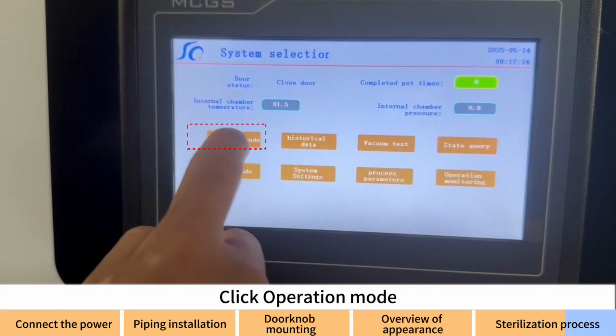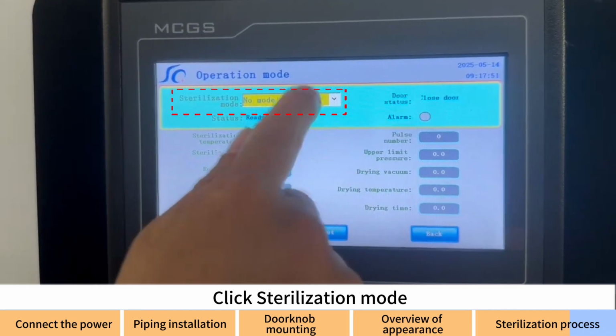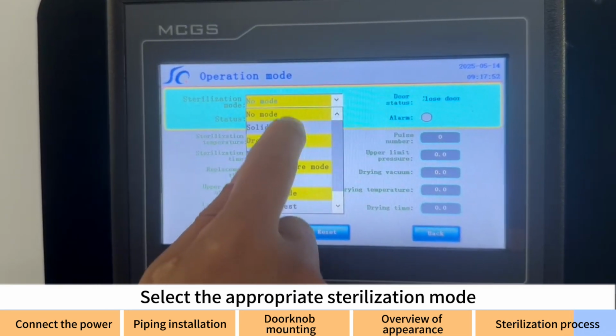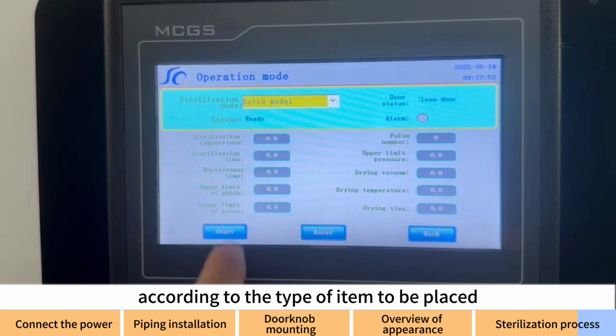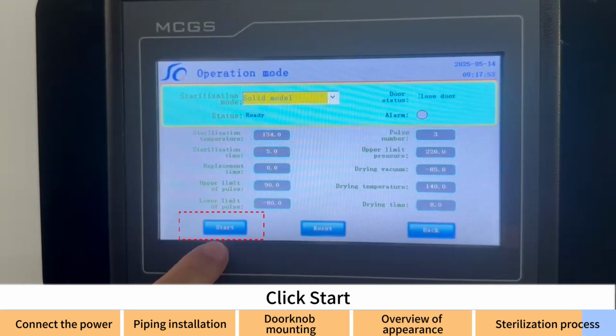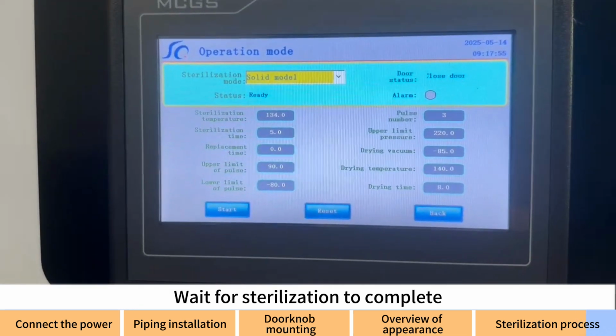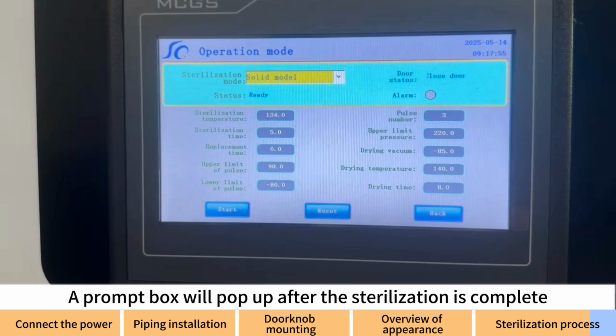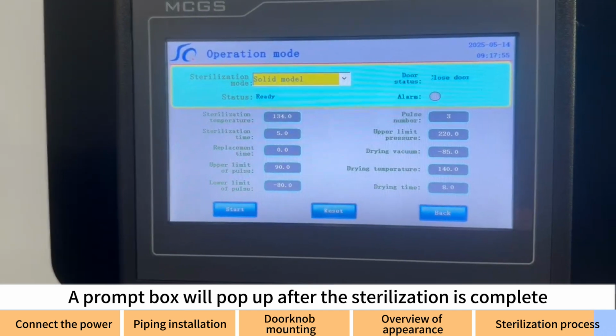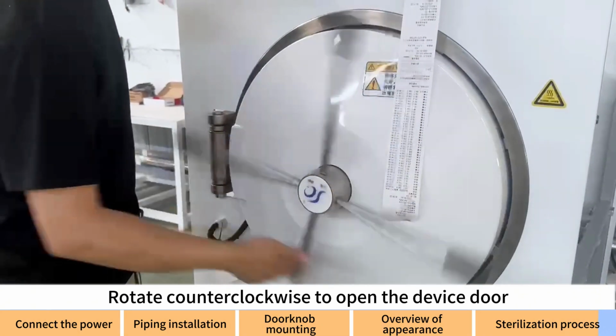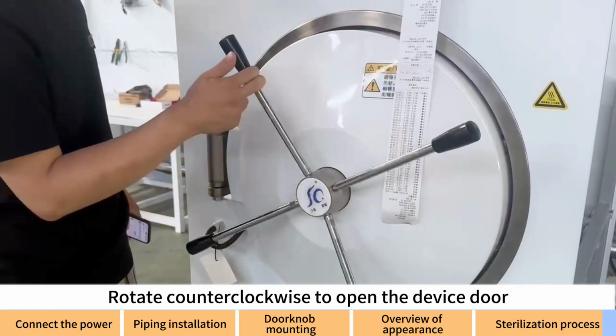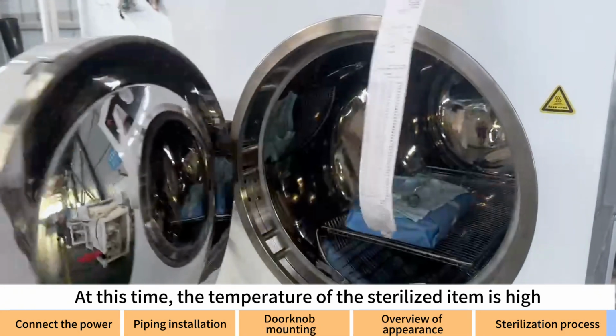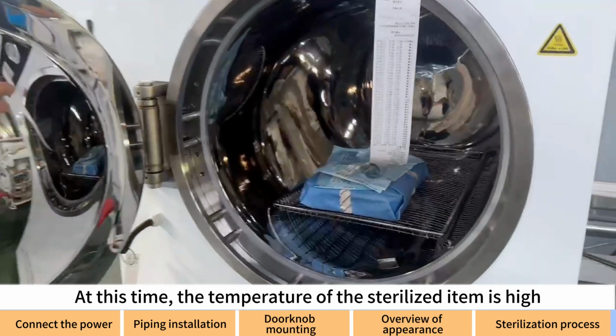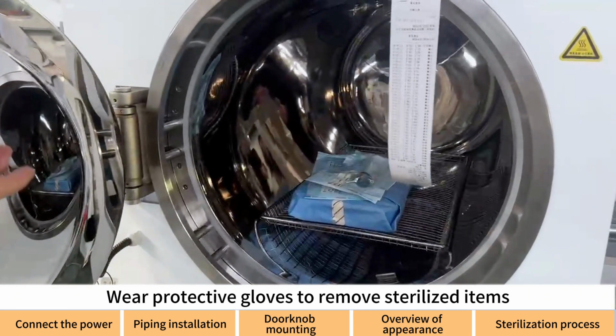Click Operation Mode. Click Sterilization Mode. Select the appropriate sterilization mode according to the type of item to be placed. Click Start. Wait for sterilization to complete. A prompt box will pop up after the sterilization is complete. Rotate counterclockwise to open the device door. At this time, the temperature of the sterilized item is high. Wear protective gloves to remove sterilized items.